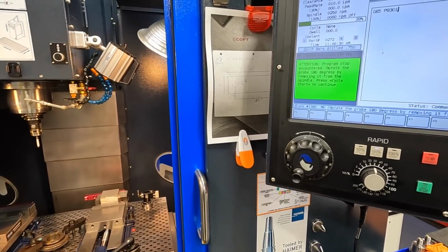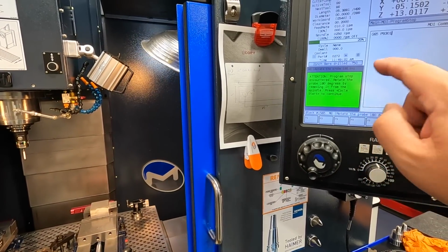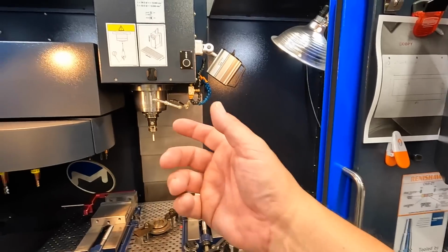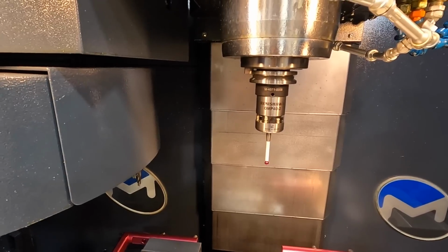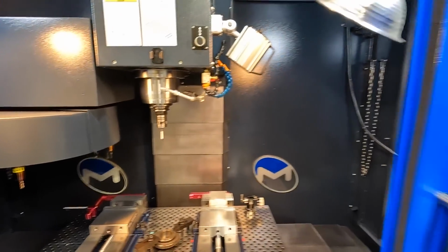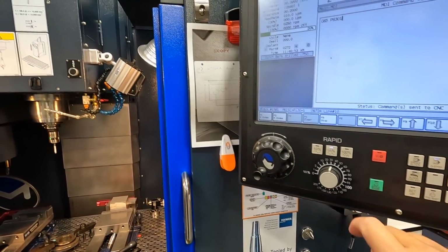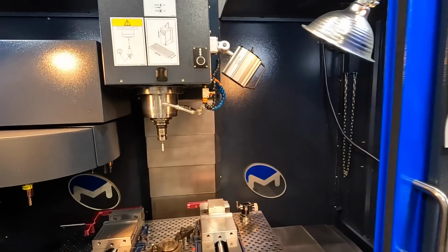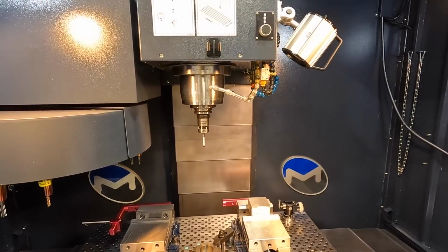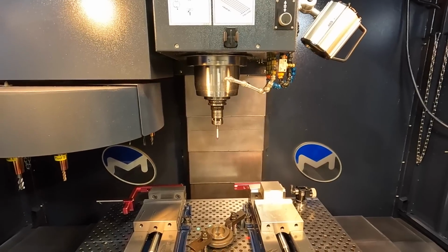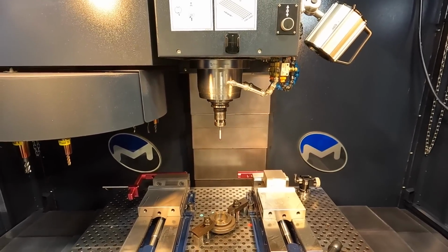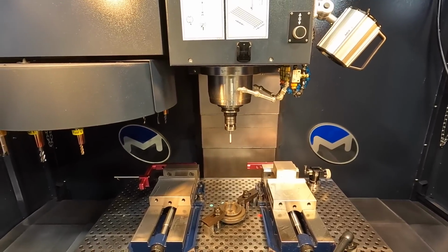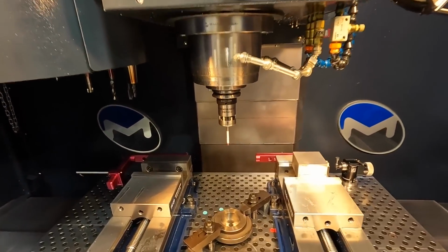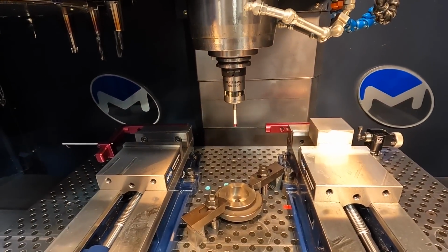Program stop encountered, rotate the probe 180 degrees, and then hit cycle start to continue. So we'll go ahead and flip it 180. All right, just installed the tool 180 degrees. Cycle start. So I believe it's going to come down and just do the same thing again. And it's going to average out all of the contact points that it's measuring to find the average of the center.